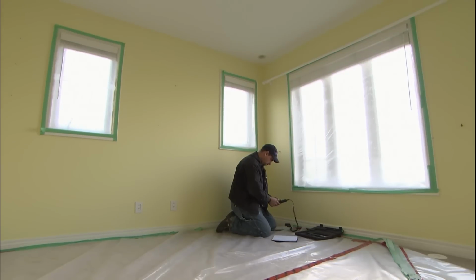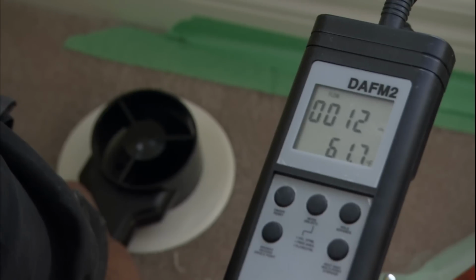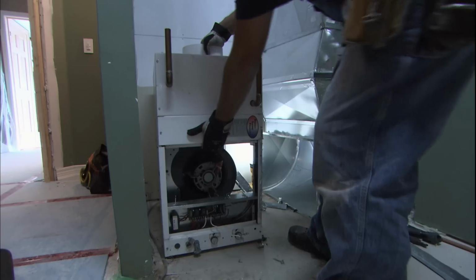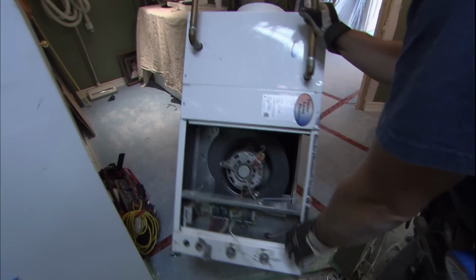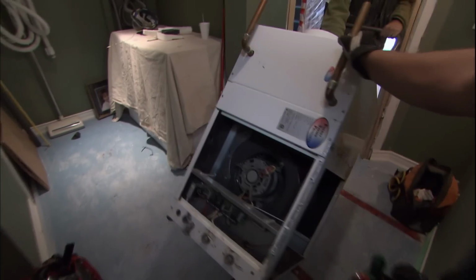We did the same tests and found a wide variety of airflow per vent or outlet throughout the house. We do know why your air conditioner went out — it's a 3-ton unit, but they put in a 5-ton cooling coil, which is an absolute no. That just smothered your air conditioner and burnt it out.